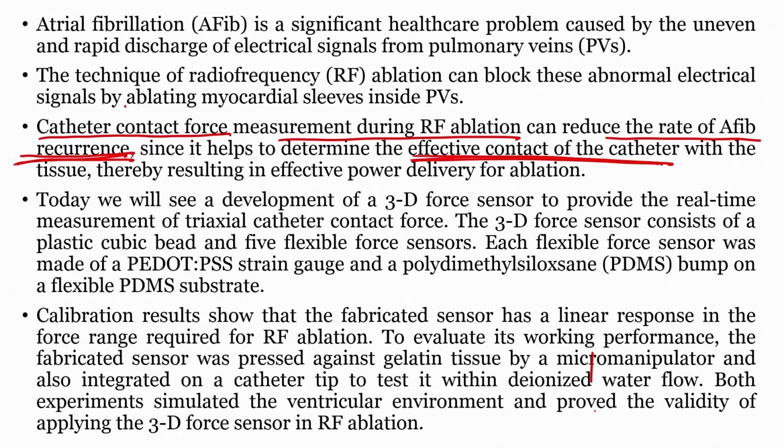Now, for that, we will see the development of a 3D force sensor that we have worked on in the laboratory to provide real-time measurement of a triaxial catheter contact force. The 3D force sensor consists of a plastic cubic bead and 5 flexible force sensors.